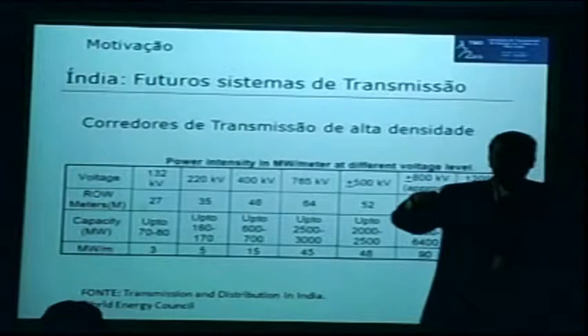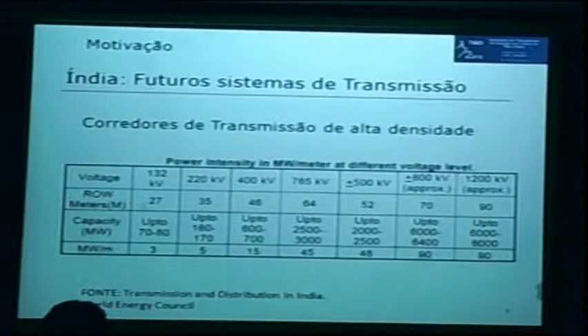Talking about India and their system, take a look at the index they placed. For voltage level, or the highest voltage levels, they maximize the megawatts per transmitted meter. Here we have the right-of-way, how wide it is, and the voltage levels, the capacity of installed transmitted power. In India, they go for 1,200 kV when they can optimize the use of the right of way, with 90 megawatts per meter.